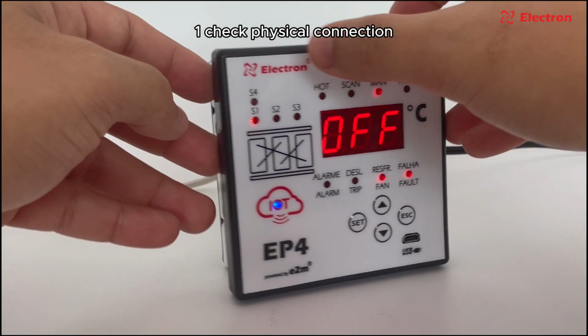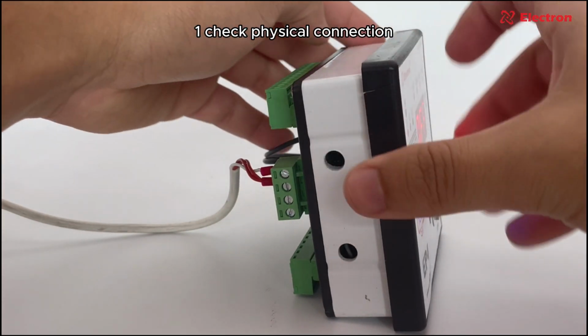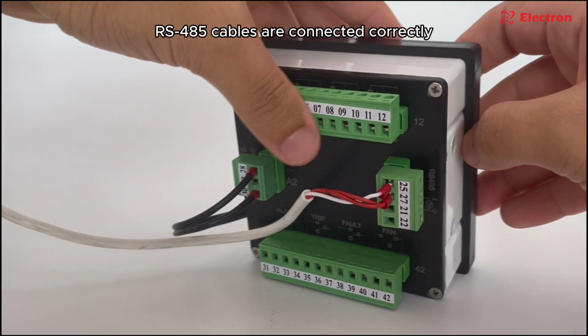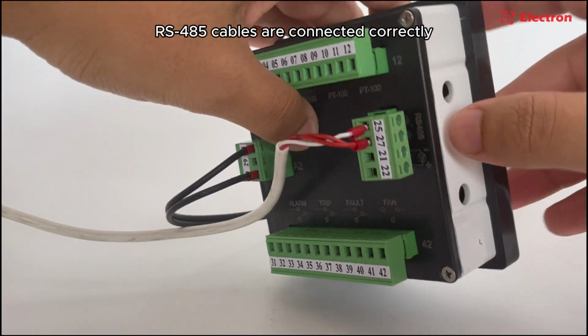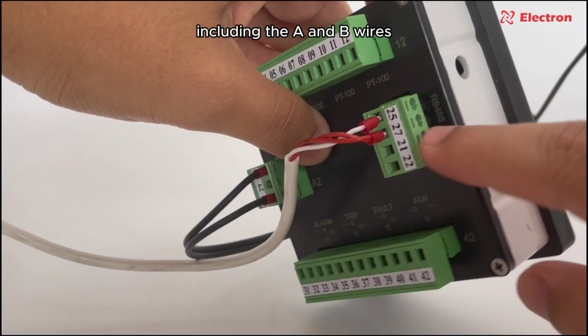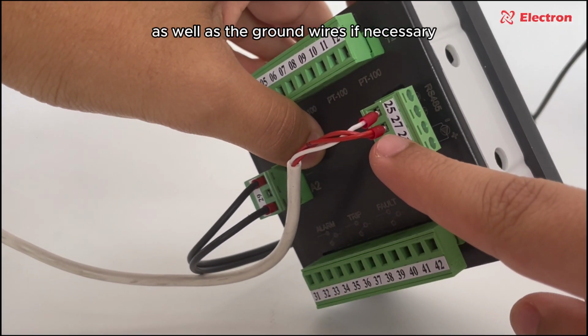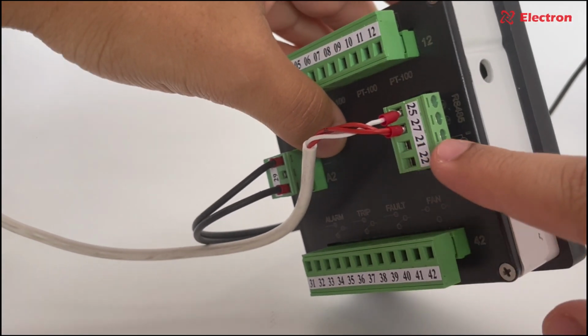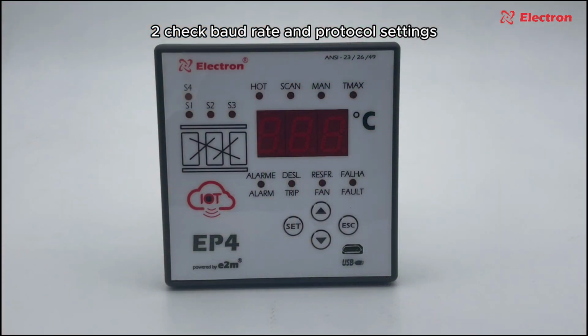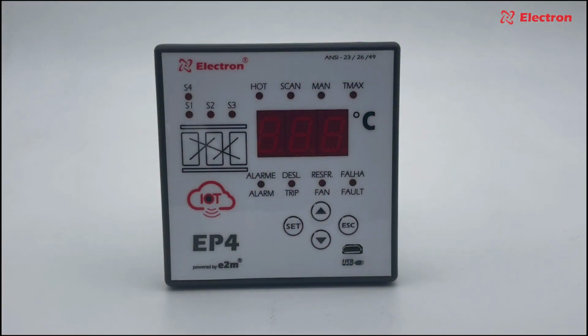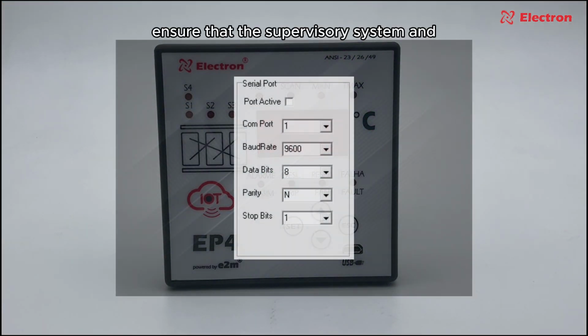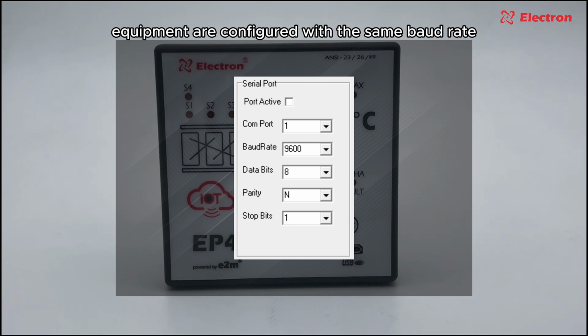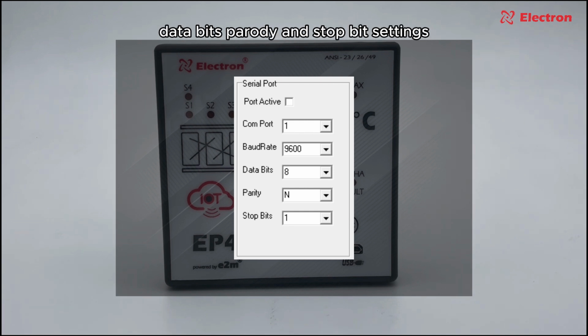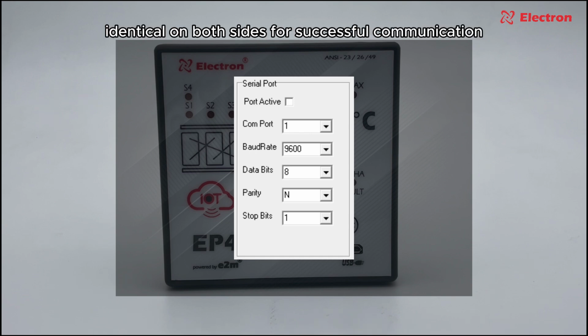1. Check physical connection. Make sure all RS-485 cables are connected correctly, including the A and B wires, as well as the ground wires if necessary. 2. Check baud rate and protocol settings. Ensure that the supervisory system and equipment are configured with the same baud rate, data bits, parity, and stop bits settings. These settings must be identical on both sides for successful communication.